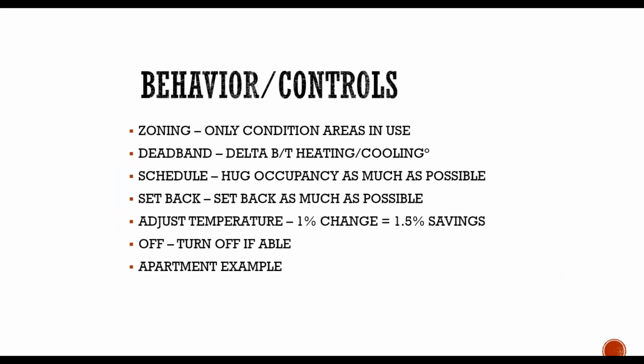So, behavior and controls: just a few things, and I go through these a little more on other slides. Zoning comes on the next slide. Deadband, the second one, is something to keep in mind. If your cooling set point is 72 degrees and your heating set point is 70 degrees, typically each set point has a 2-degree differential. If you only have a 2-degree deadband, more than likely you're having simultaneous heating and cooling because the set points overlap. So what I encourage a lot of churches to do is either use heating or cooling only, or in between months, have a 5 to 6 degree deadband.